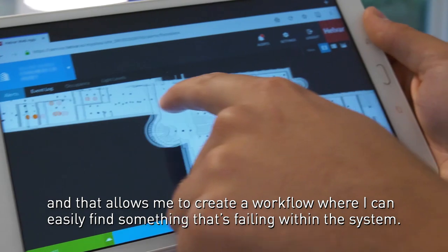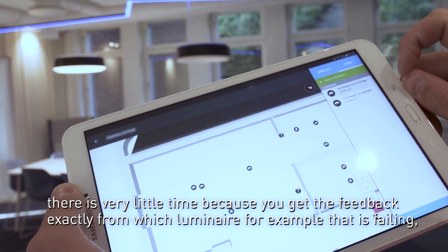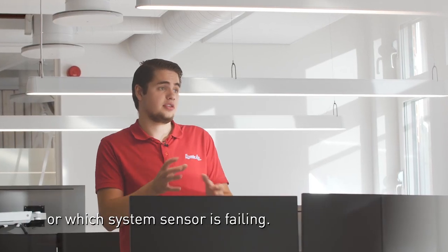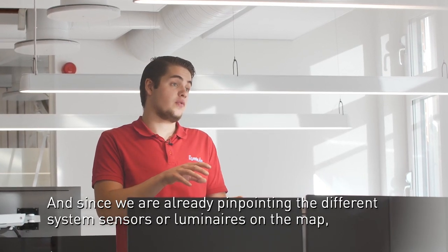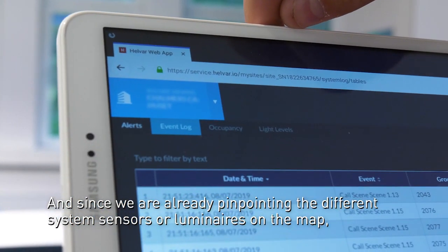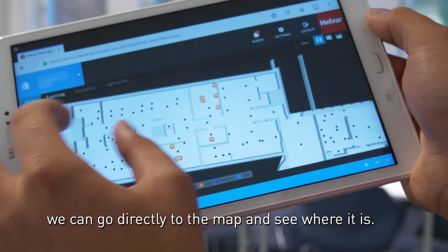That allows me to create a workflow where I can easily find something that's failing within the system. From identifying a fault to finding it, there's very little time because you get feedback exactly from which luminaire or which system sensor is failing, and since we have already pinpointed the different system sensors or luminaires on the map, we can go directly to the map and see where it is.